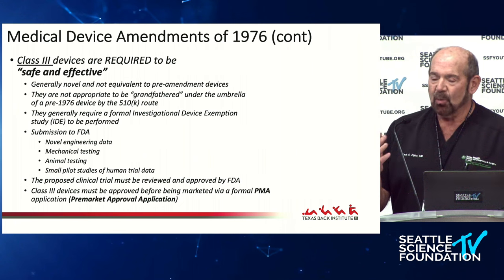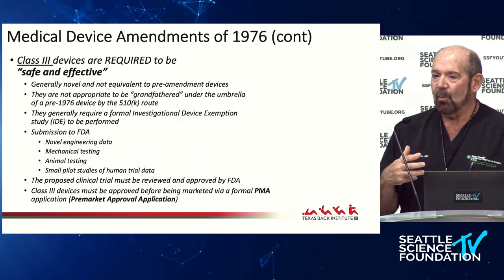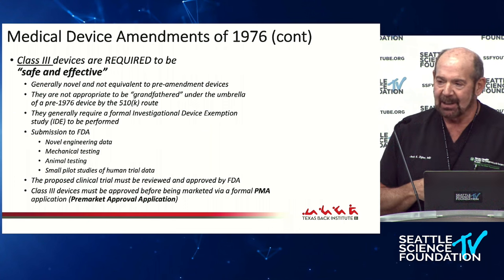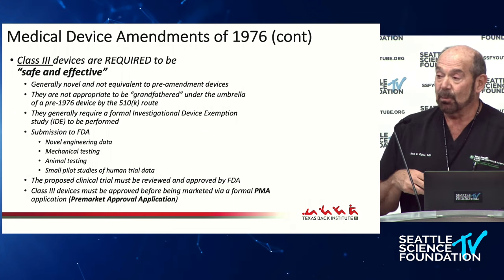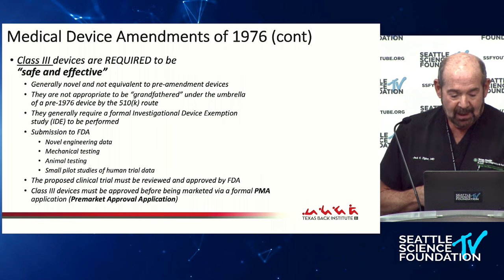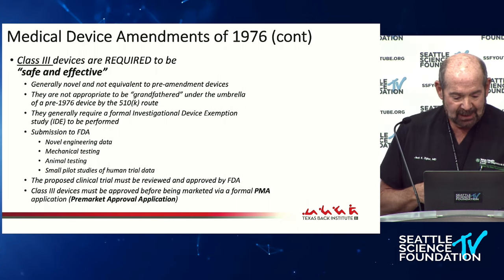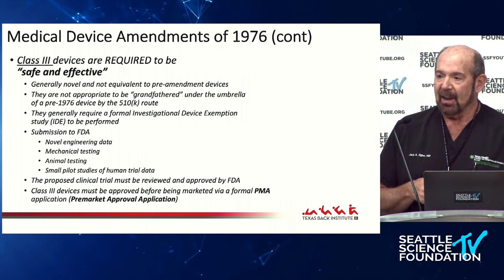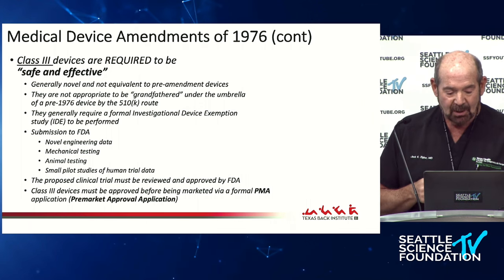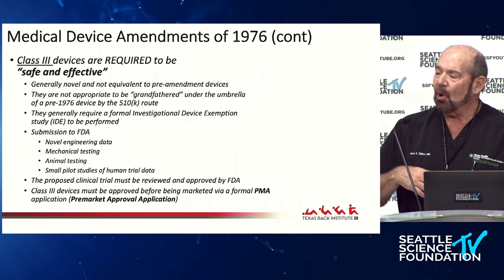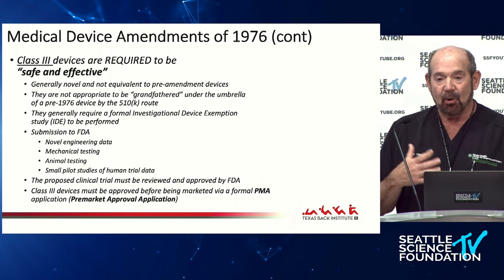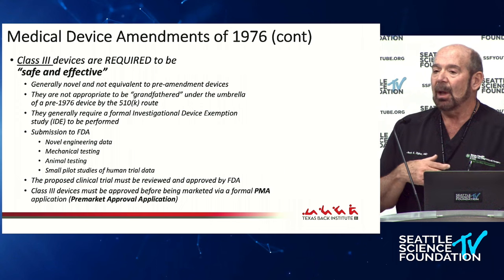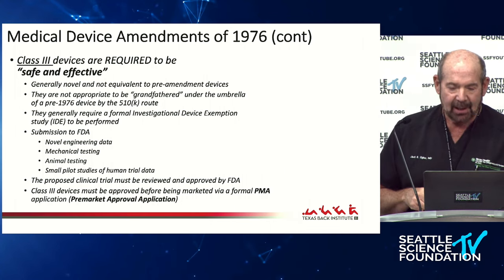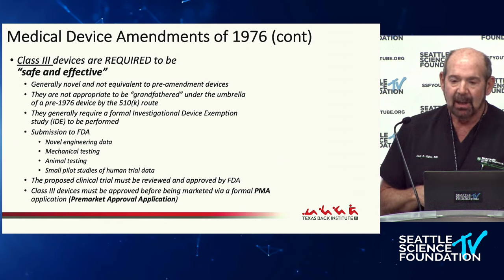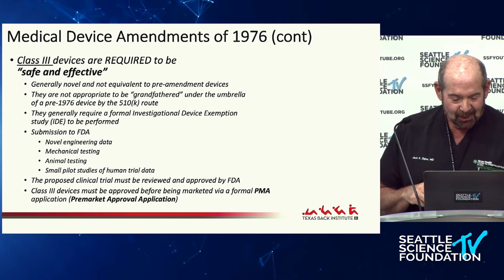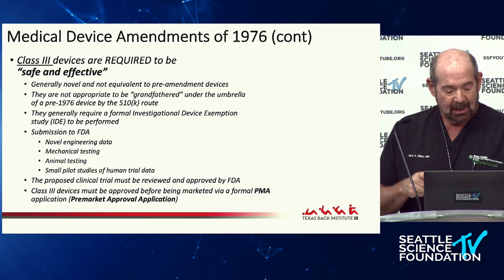Class three devices were novel technology, which had no predicate prior to 1976, and they had to prove also that they were going to be safe and effective. They could not be grandfathered in by a 510K path. They would require a formal investigational device exemption study, an IDE study, and required multiple submissions to the FDA even to be granted the ability to do that. They had to show what's novel, show the engineering data, show some basic mechanical testing, some animal testing, as we talked about a little earlier, and sometimes even a small pilot study on humans.